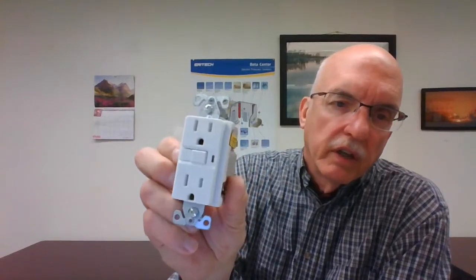Well, before the 2014 came into effect, it was code compliant to just replace a 2-prong receptacle with a 2-prong receptacle because there was nothing else you could do. But now, if you have to replace a receptacle in a room where arc fault protection is needed today, it must be provided with arc fault protection when you replace it. All right, so that means you're going to have to install like this. Okay, this is an arc fault.